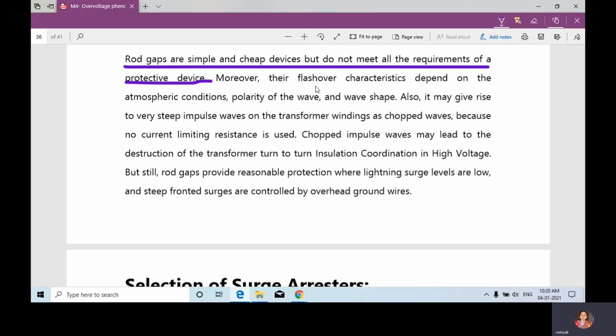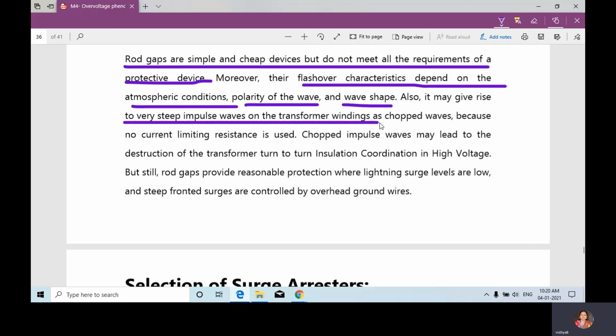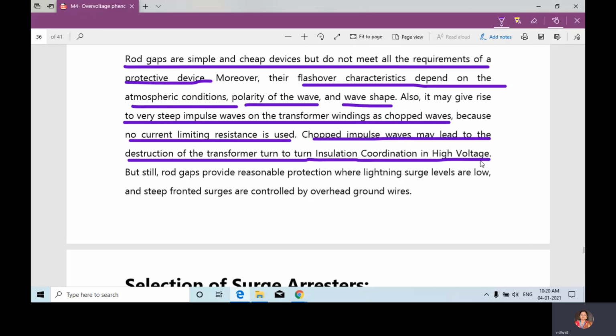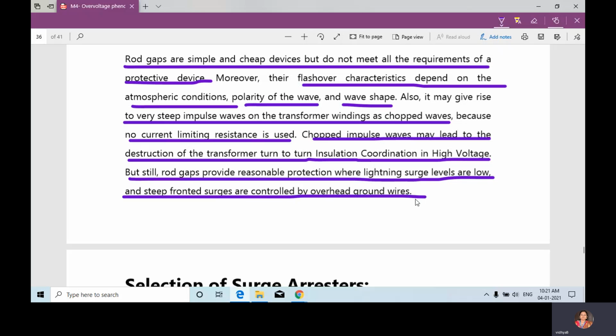The flashover characteristics will depend on the atmospheric conditions, polarity of the wave, and wave shape also. It may give rise to very steep impulse waves on the transformer windings as chopped waves, because no current limiting resistance is used. Chopped impulse waves may lead to the destruction of the transformer turn-to-turn insulation coordination in high voltage. But still, rod gaps provide reasonable protection where lightning surge levels are low and steep fronted surges are controlled by overhead ground wires.